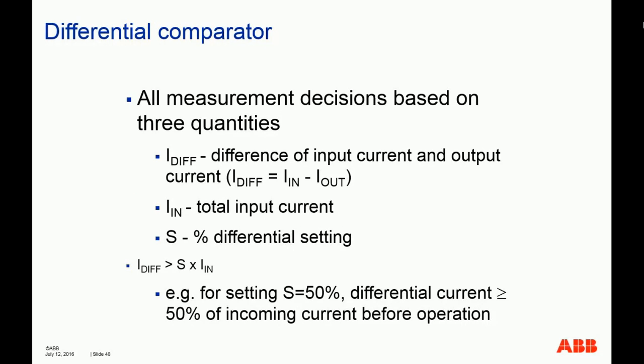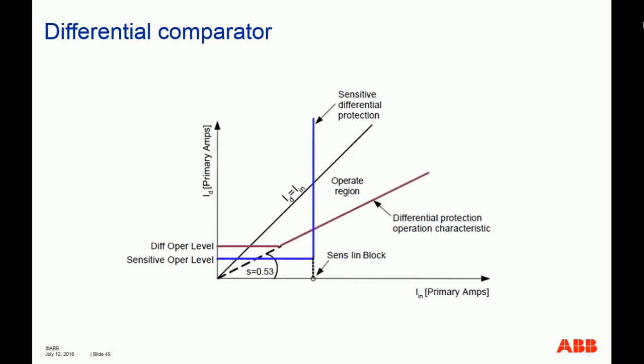So again, the same idea. Differential is based on input minus output, but this time the current values are numerically calculated. And then there's a set percentage based on settings. You will see this familiar slope here, where the operating region is above the slope and the restraint region is below the slope.